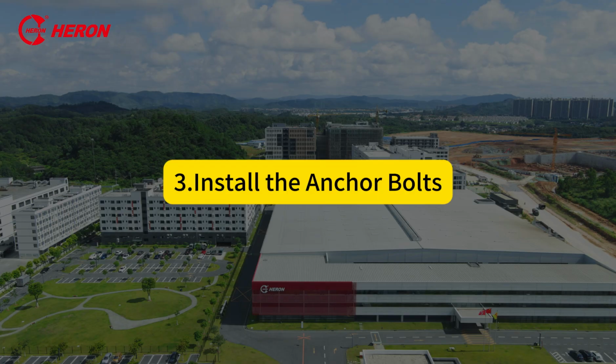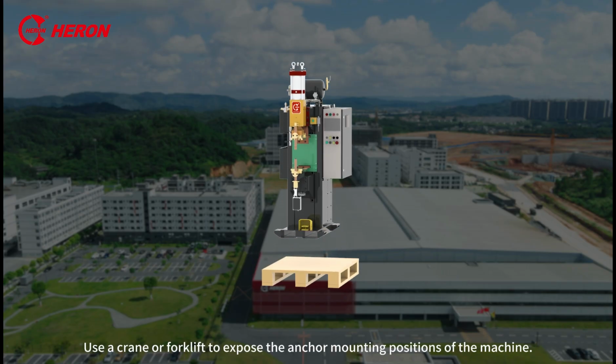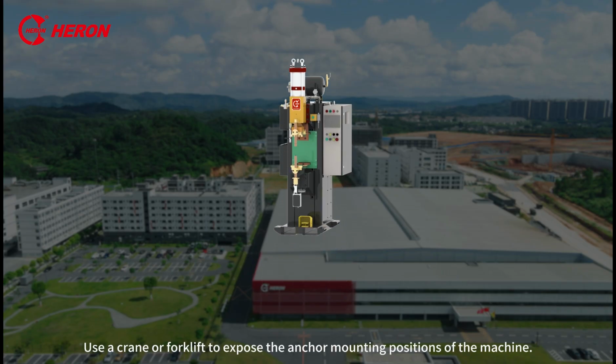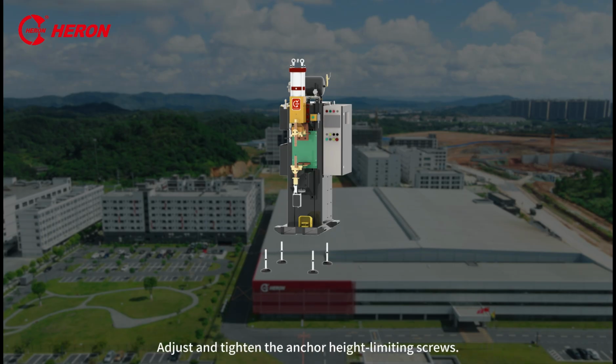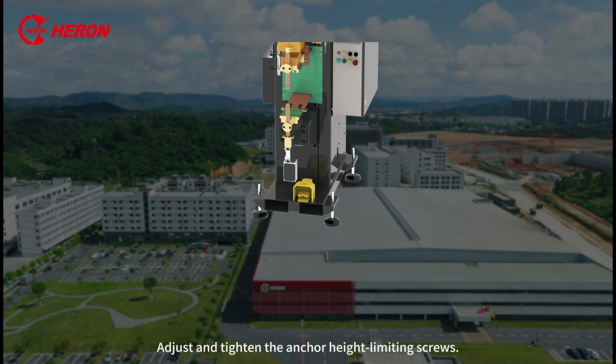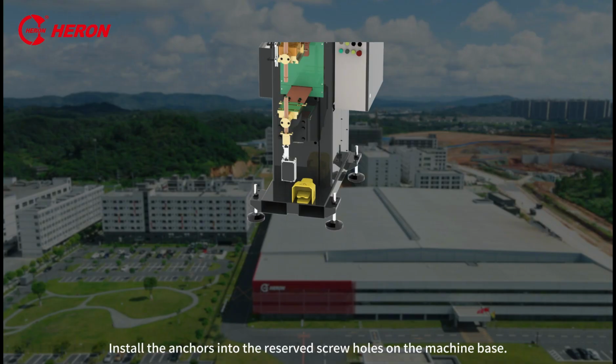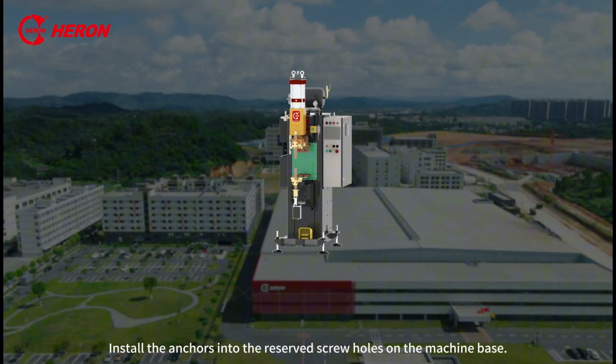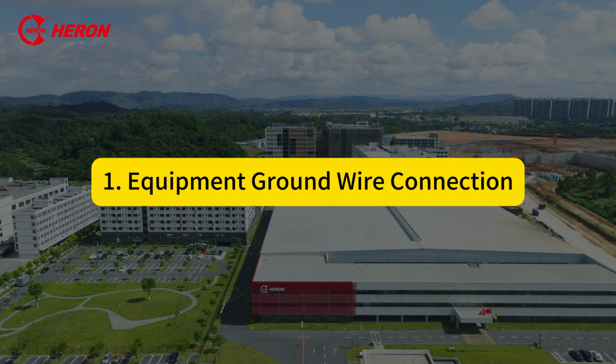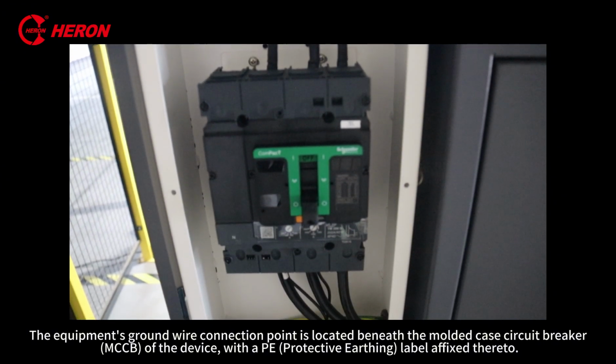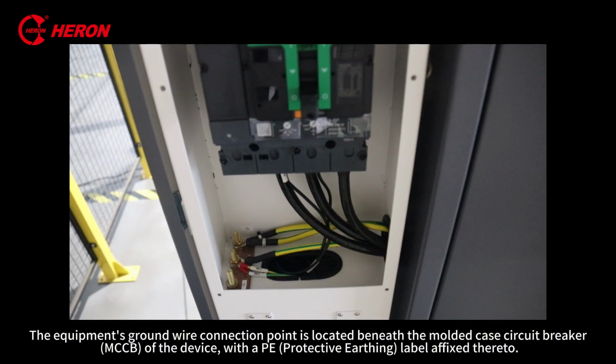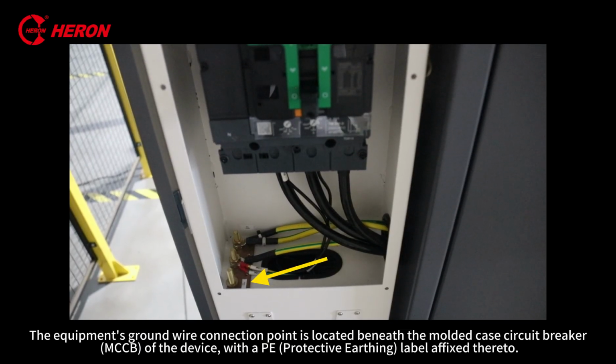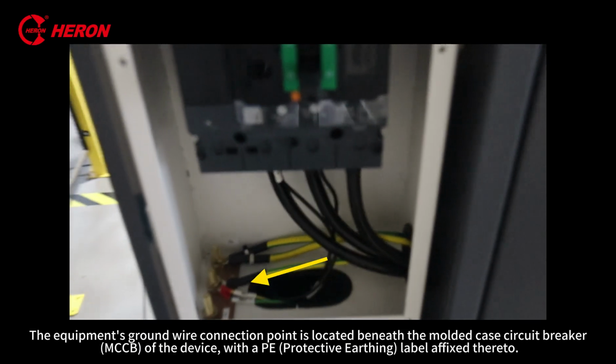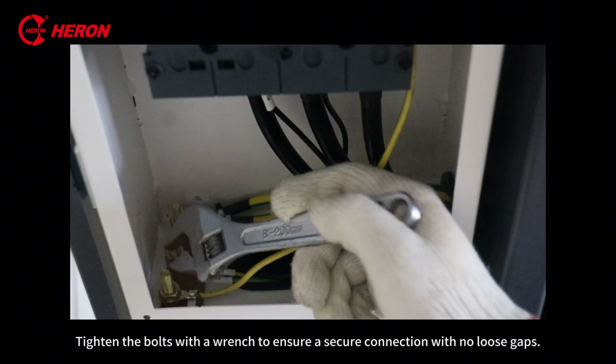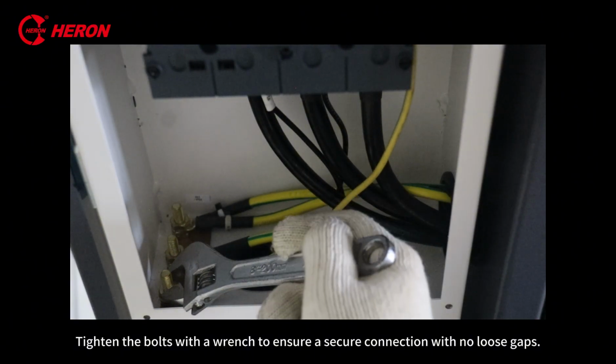3. Install the anchor bolts. Use a crane or forklift to expose the anchor mounting positions of the machine. Adjust and tighten the anchor height limiting screws. Install the anchors into the reserved screw holes on the machine base. III. Connection operation. 1. Equipment ground wire connection. The equipment's ground wire connection point is located beneath the molded case circuit breaker of the device, with a PE label affixed there. Tighten the bolts with a wrench to ensure a secure connection with no loose gaps.